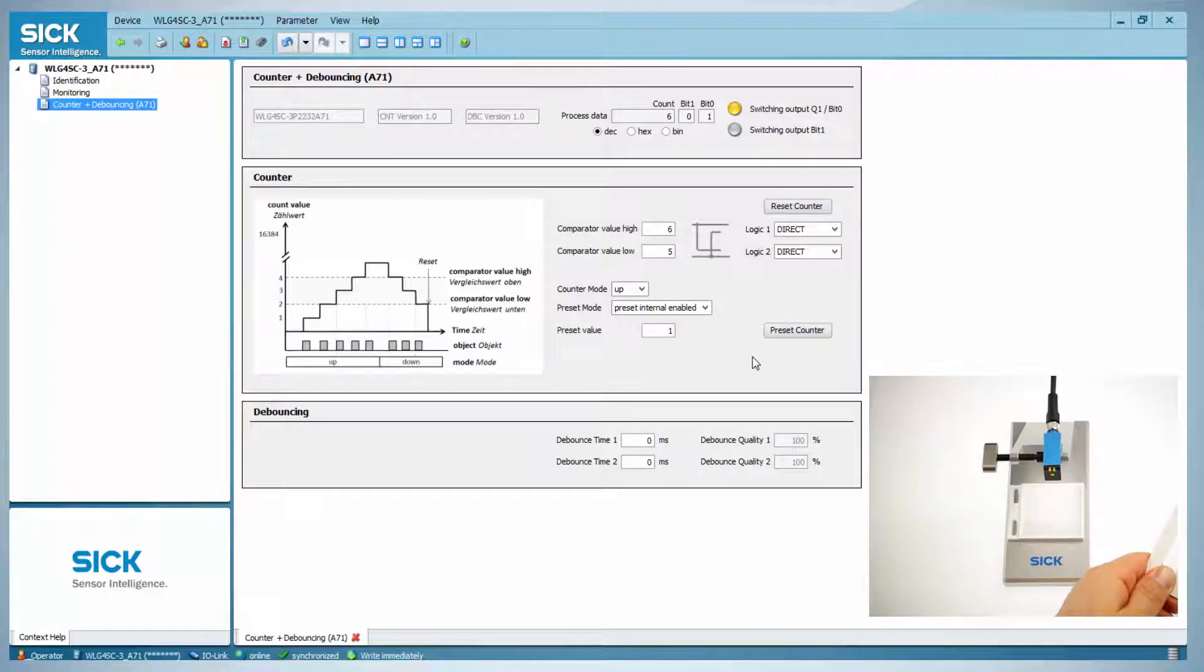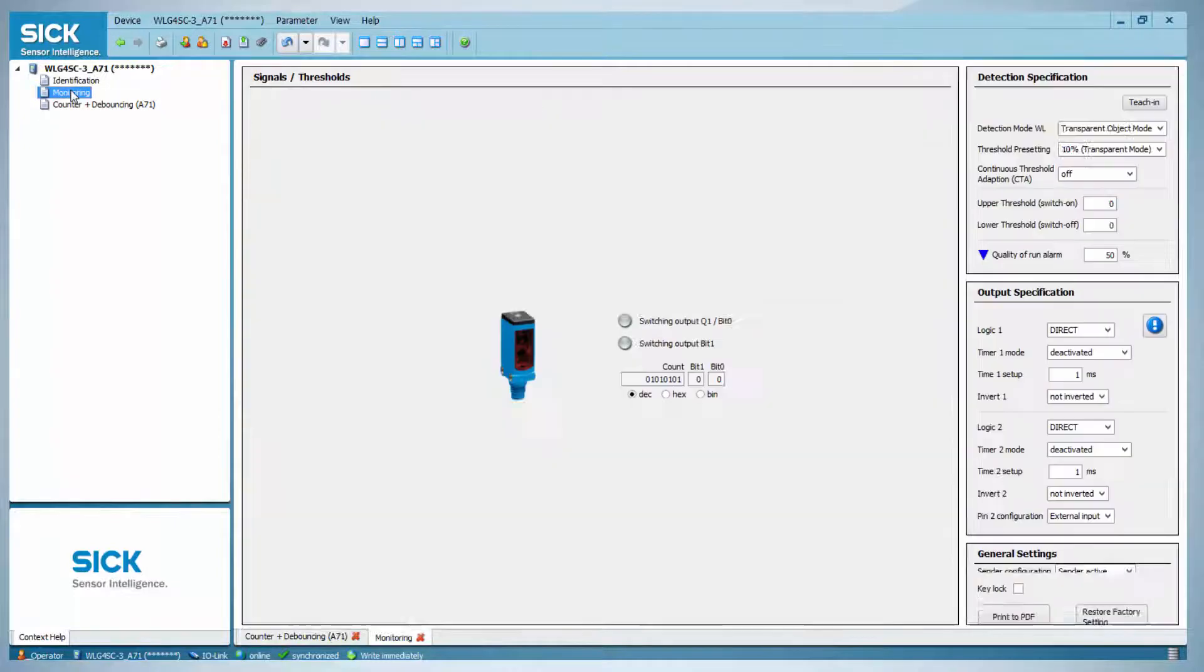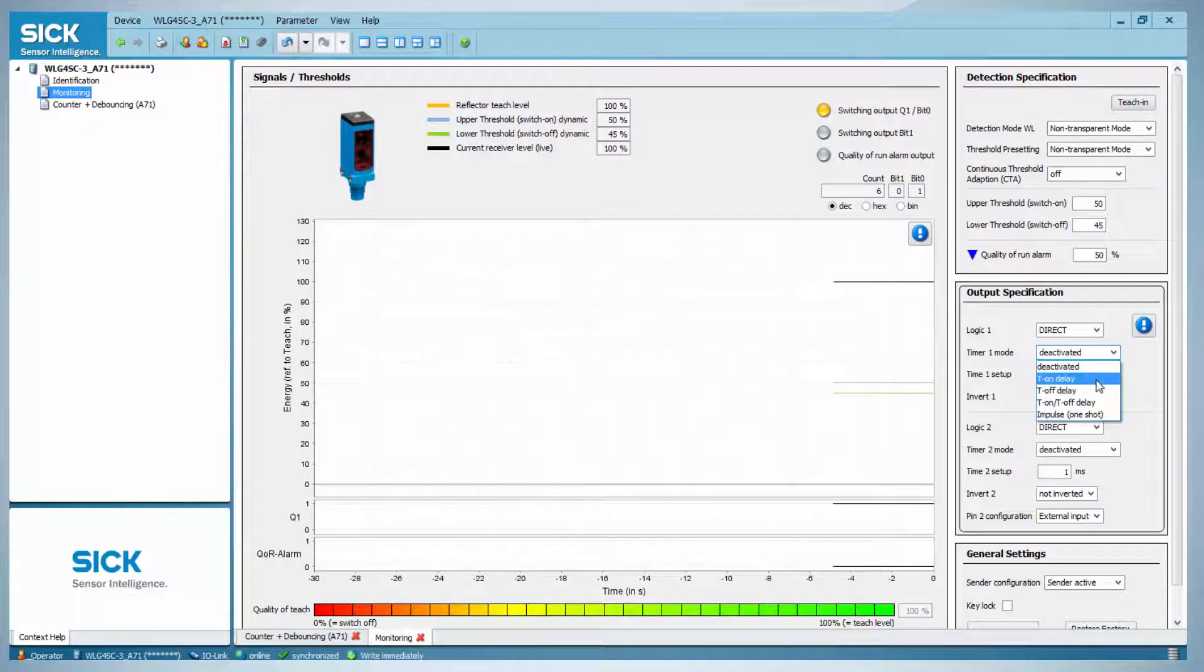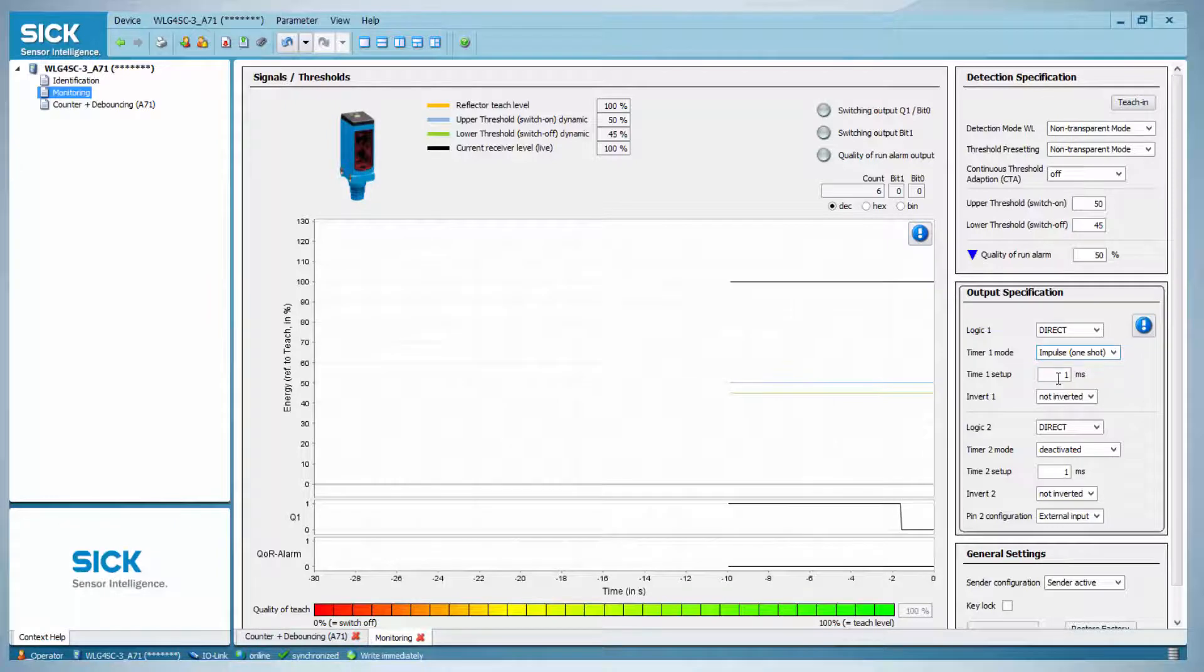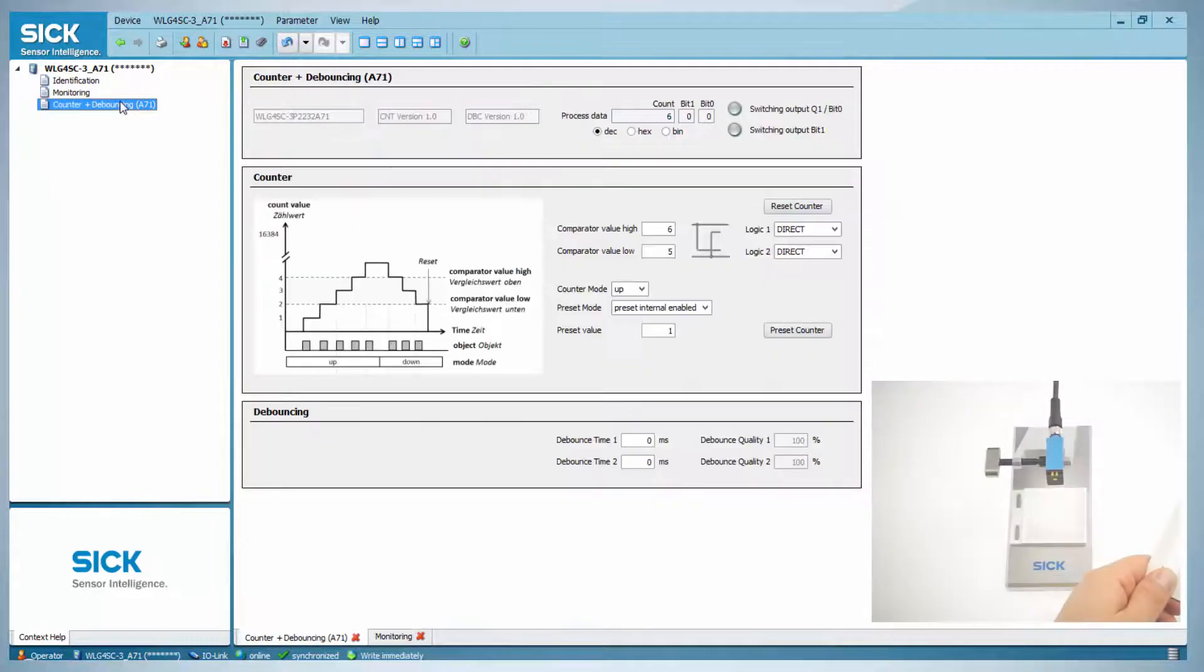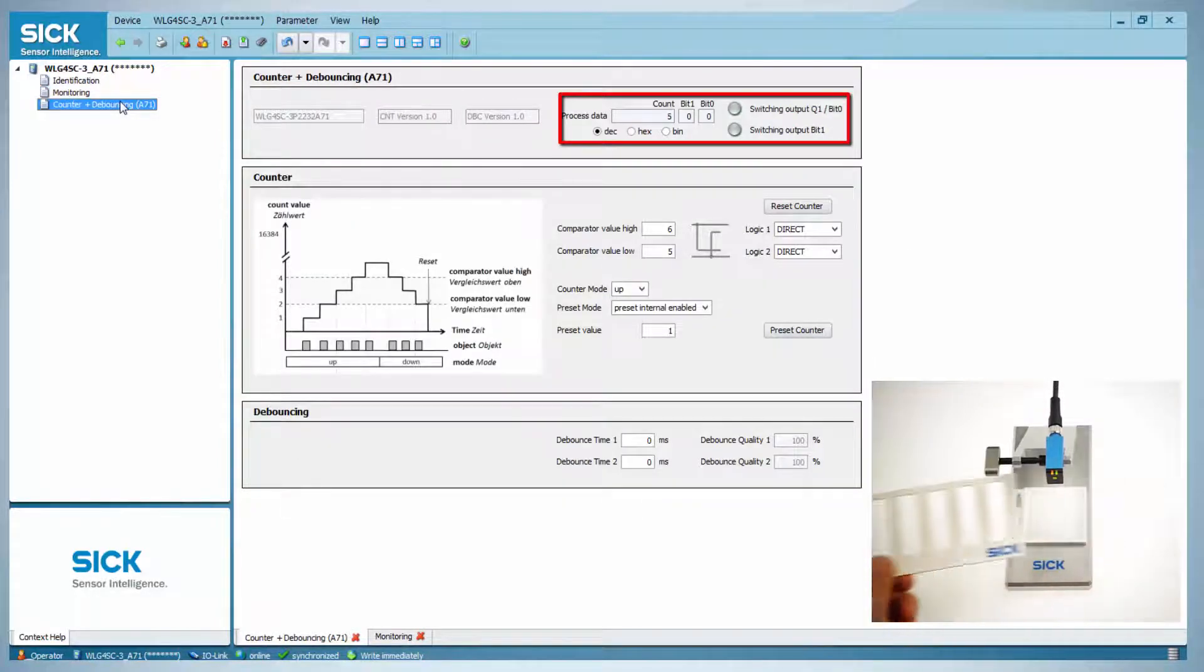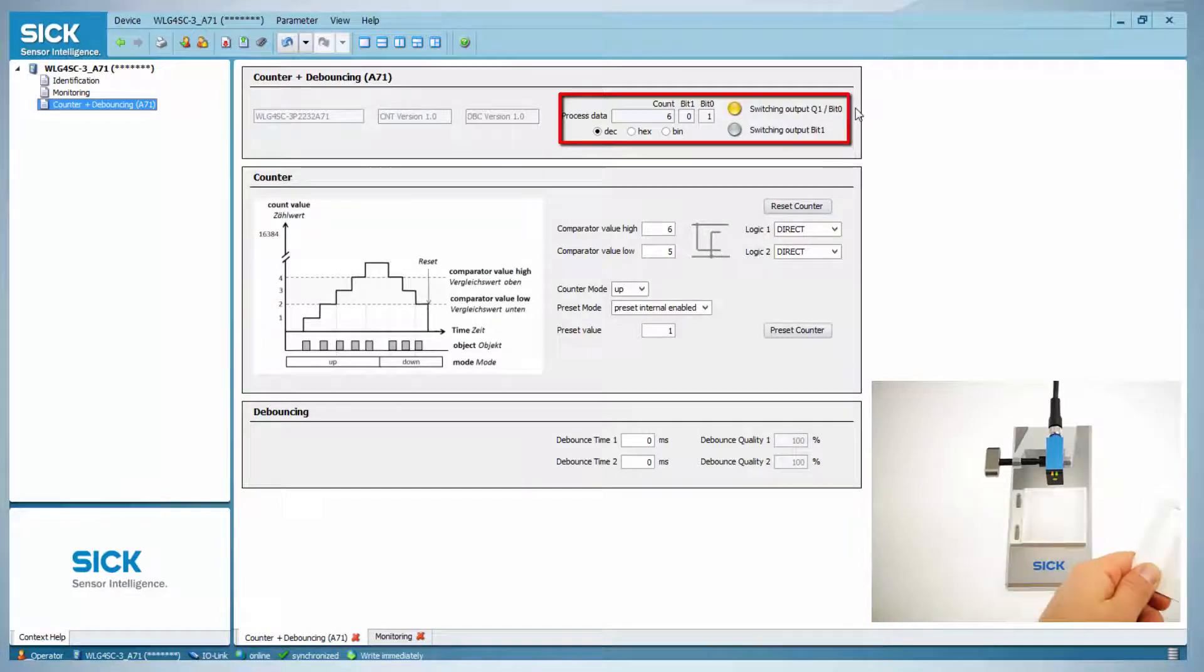The switching output can be combined with different timer modes. In order to add such a timer mode, click on monitoring and then add either an on, off, on-off delay, or one shot. As an example, a one shot is selected. The timer is set at 500 milliseconds. If the object is moved again now, the switching output 1 stays high only for 500 milliseconds.